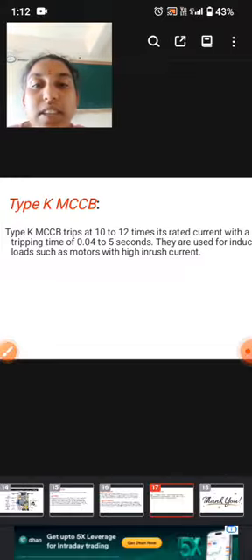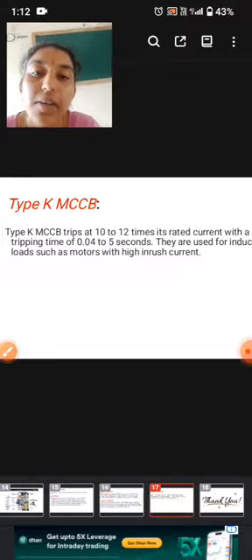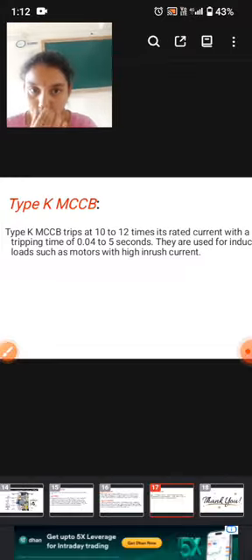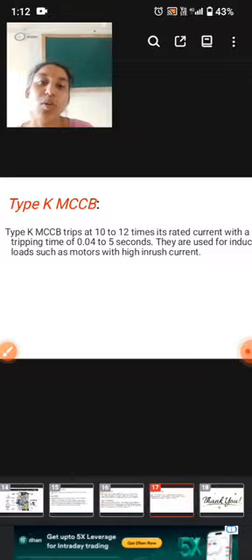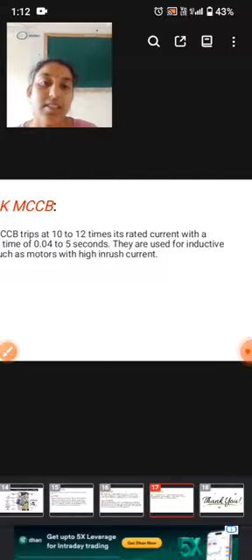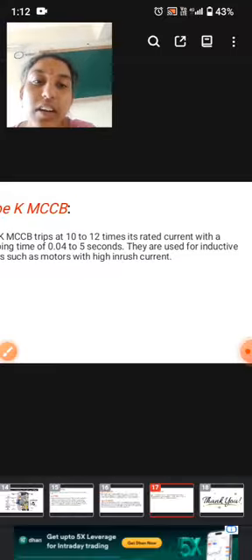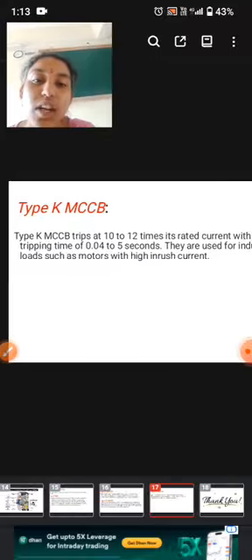The last one is type K MCCB. Type K MCCB trips at 10 to 12 times its rated current, with a tripping time of 0.04 to 5 seconds. They are used for inductive loads such as motors with high inrush currents.